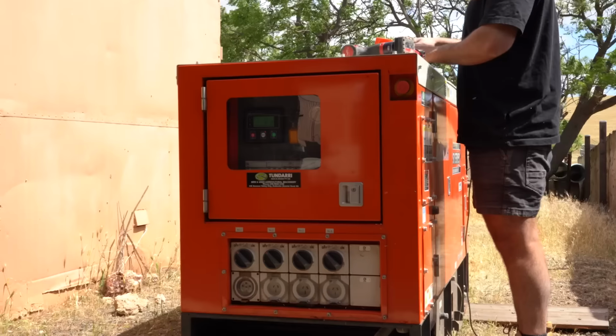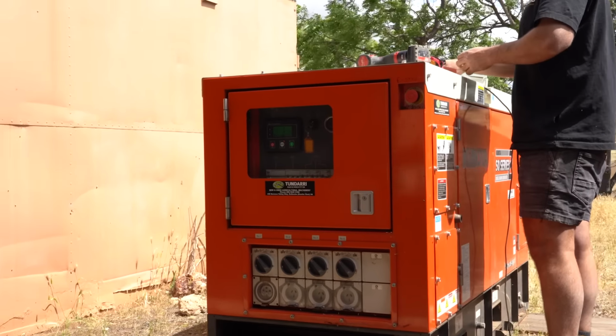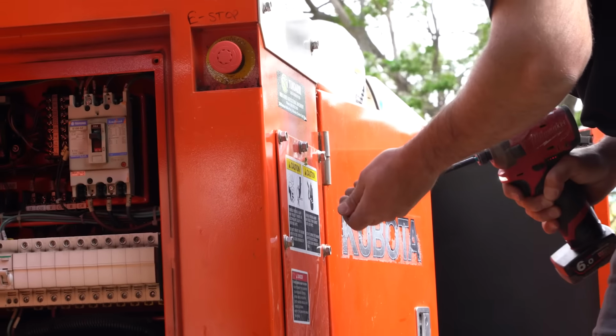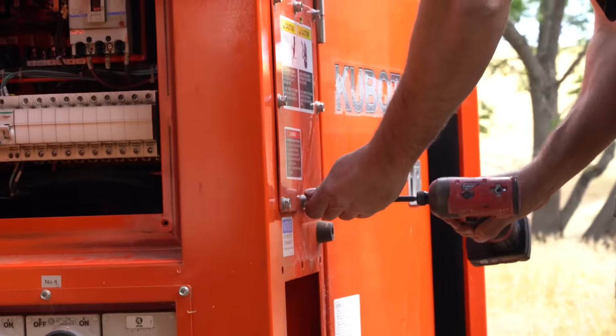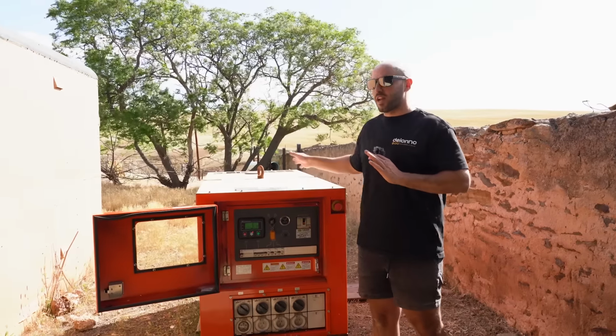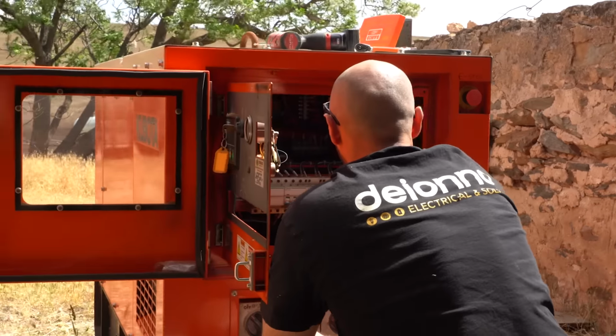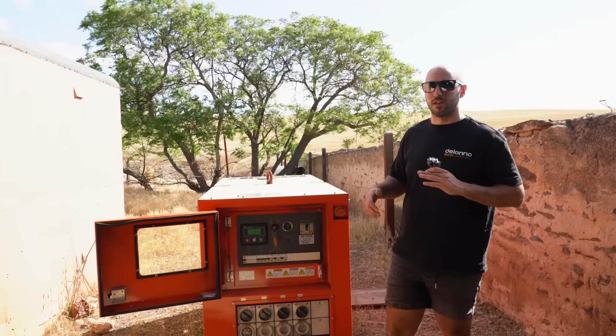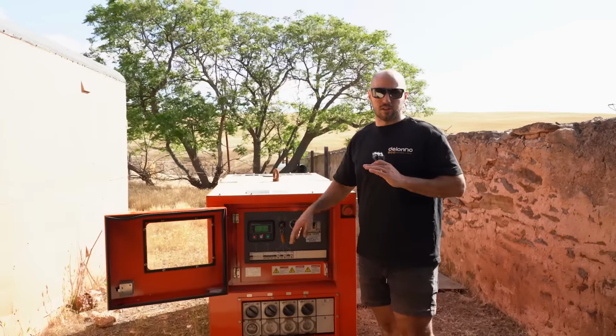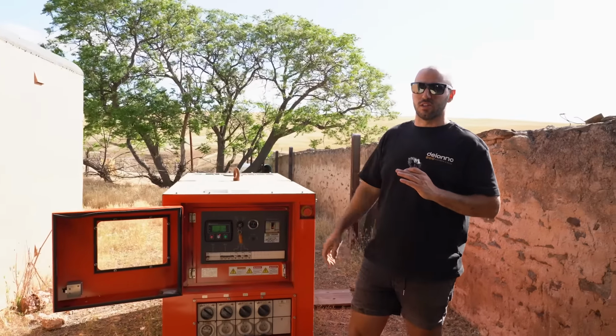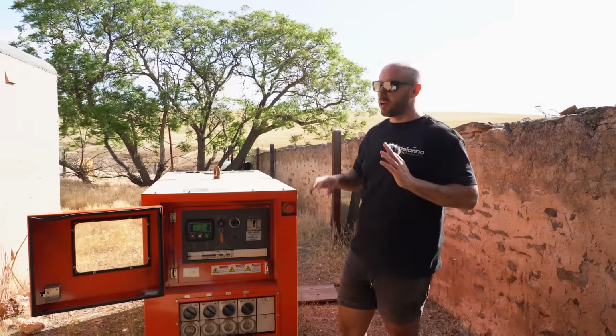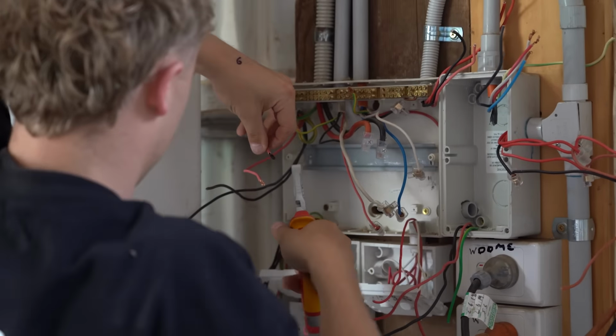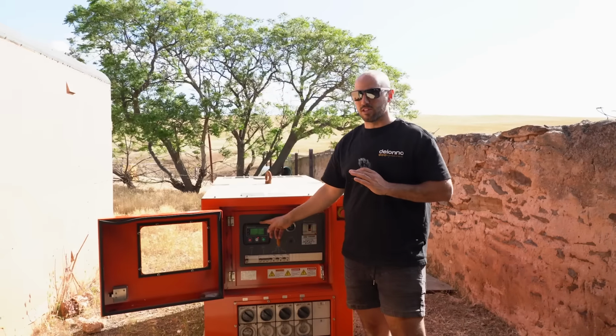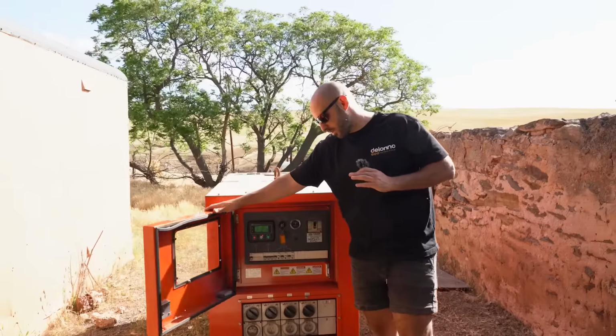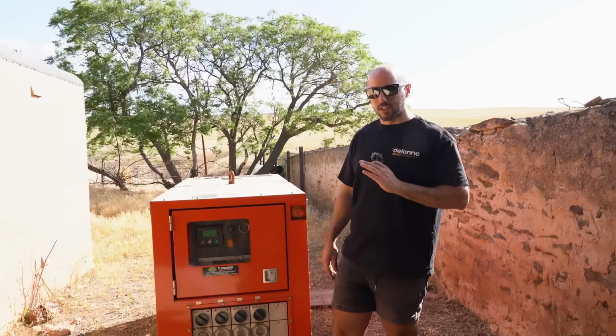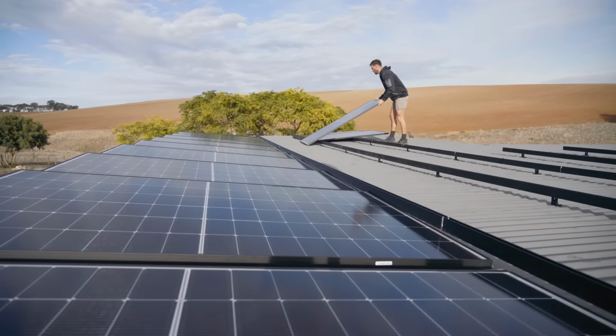These screens use so much power that over the span of a week or so, it'll actually drain the battery, so the auto start won't work. Really important for this install, where it's sitting outside in good sun, we can get a little trickle charger solar panel, or we like to build in a Victron IP rated battery charger, just a maintenance charger. Keeps it going, just in case you need to auto start the Jenny, because the MultiPlus with the Cerbo can auto start this when the batteries get low. So we do still set that up, but keep in mind these use a bit of power, so make sure you've got some backup charging happening. So that's the Jenny, nothing crazy, but good to show you anyway.